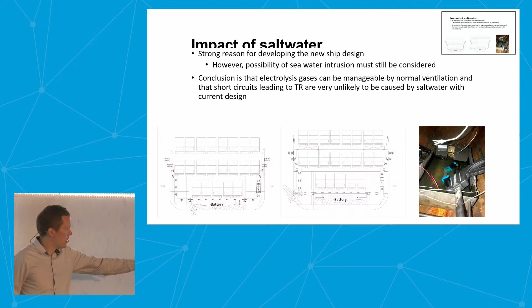of grounding, you can have salt water inside the battery room. We instead increased the margin from intrusion from the bottom, but we also said there could be other ways in case of collision, through ventilation systems and so on. So we need to look at the possibility of seawater intrusion. We did some tests on cell level with batteries in salt water, and the conclusion was that when it comes to electrolysis gases, because when you put a battery in salt water, the salt water will act as a load, and you produce hydrogen and oxygen through electrolysis. And with this size of battery installation, the conclusion was that this is manageable by the normal ventilation.